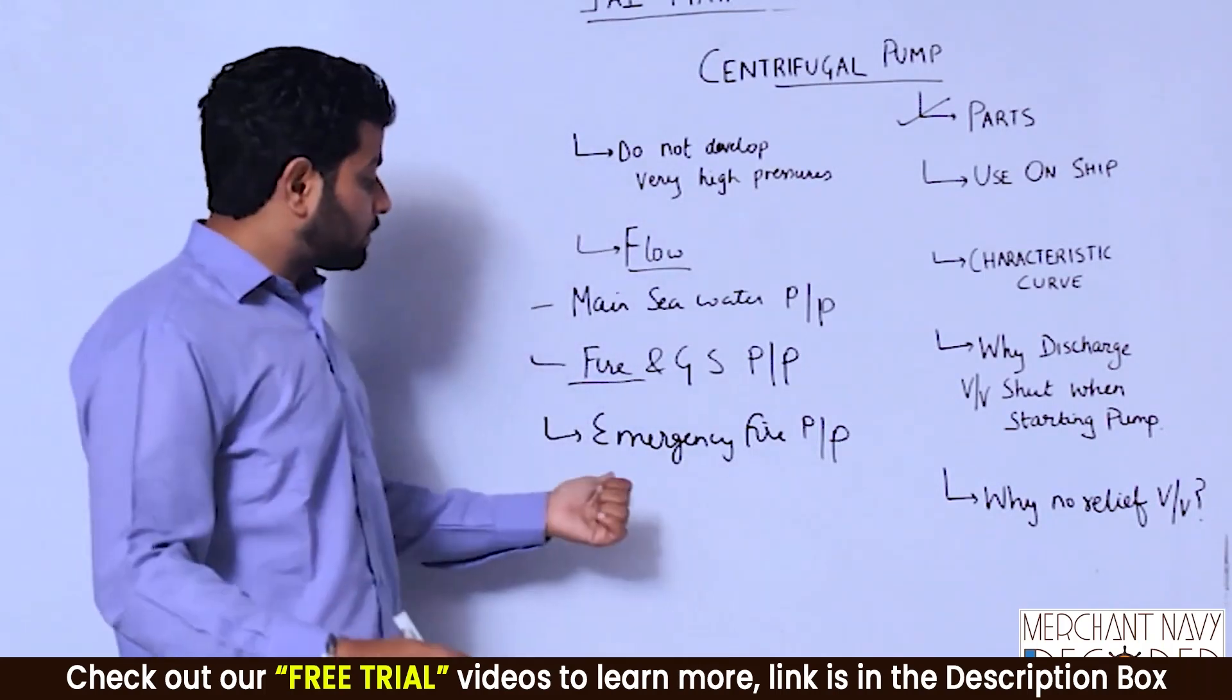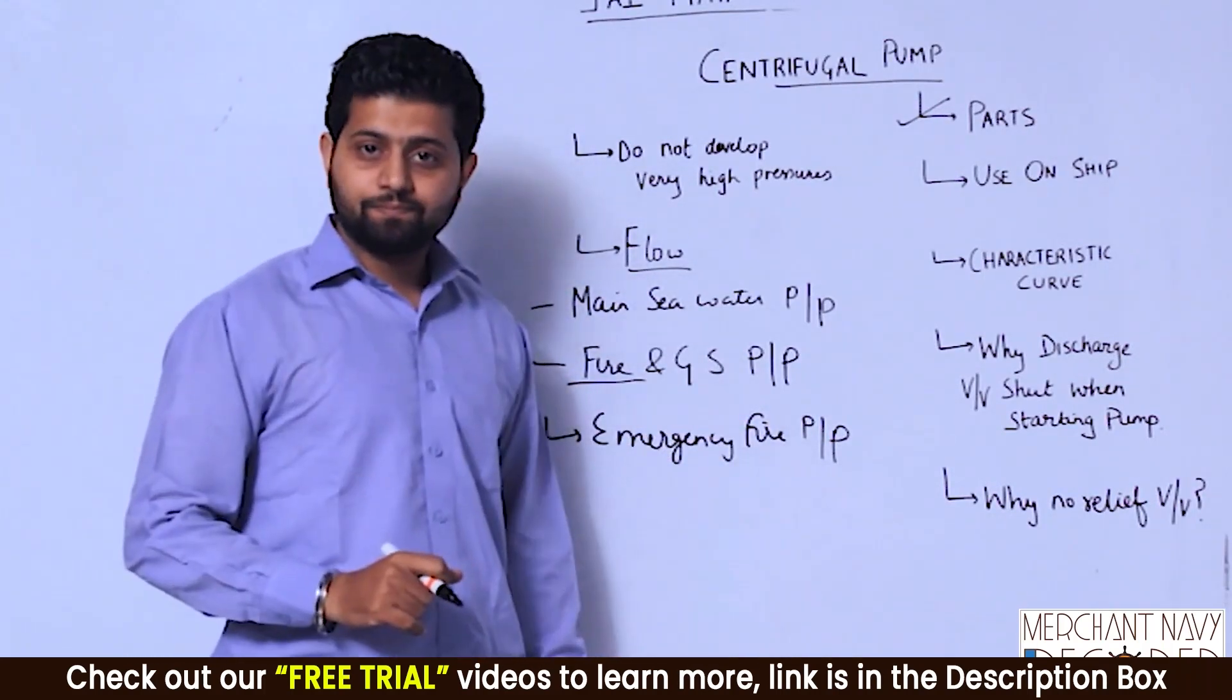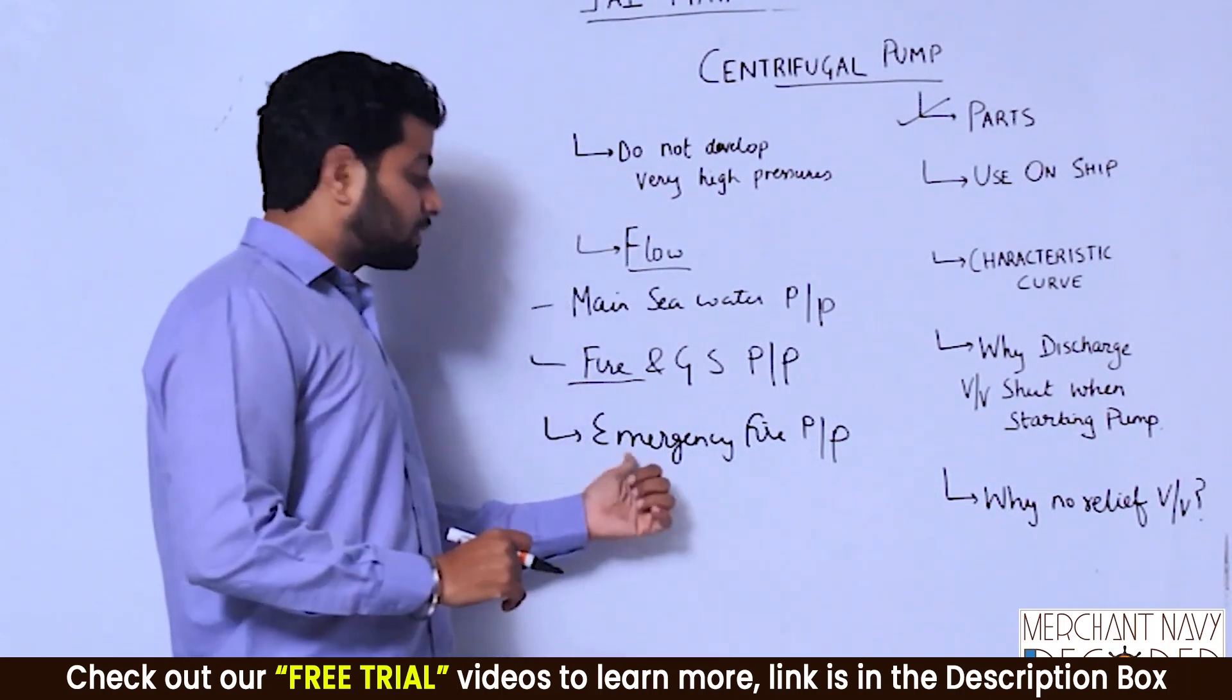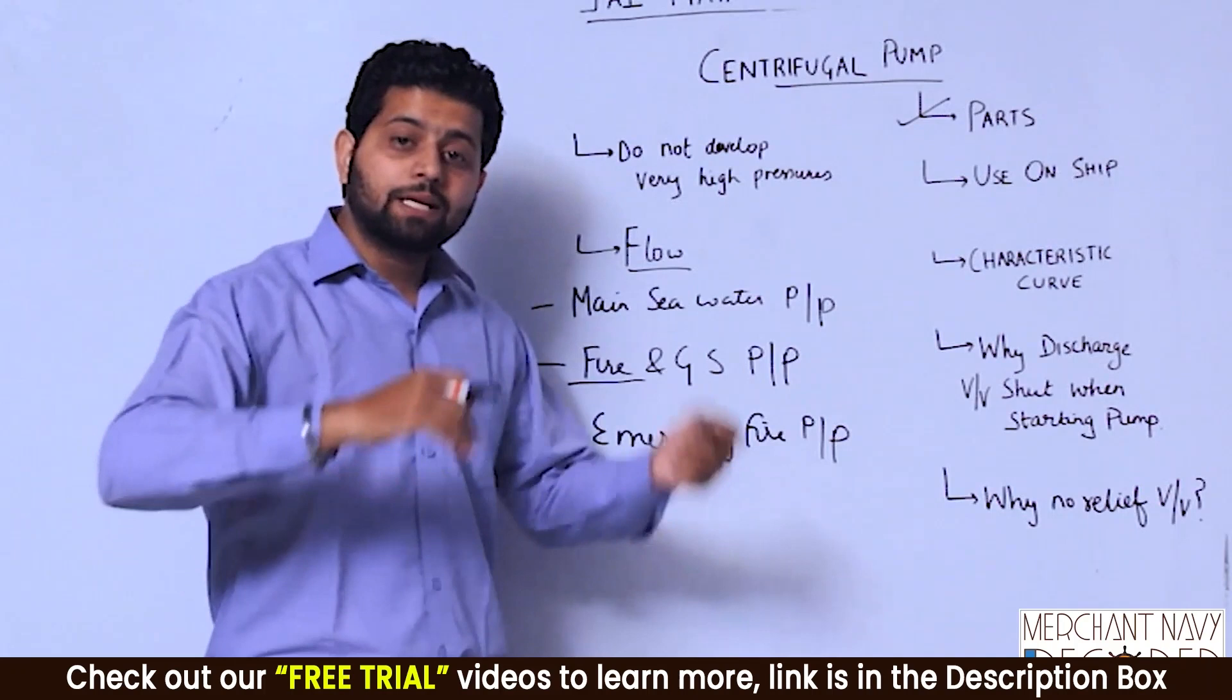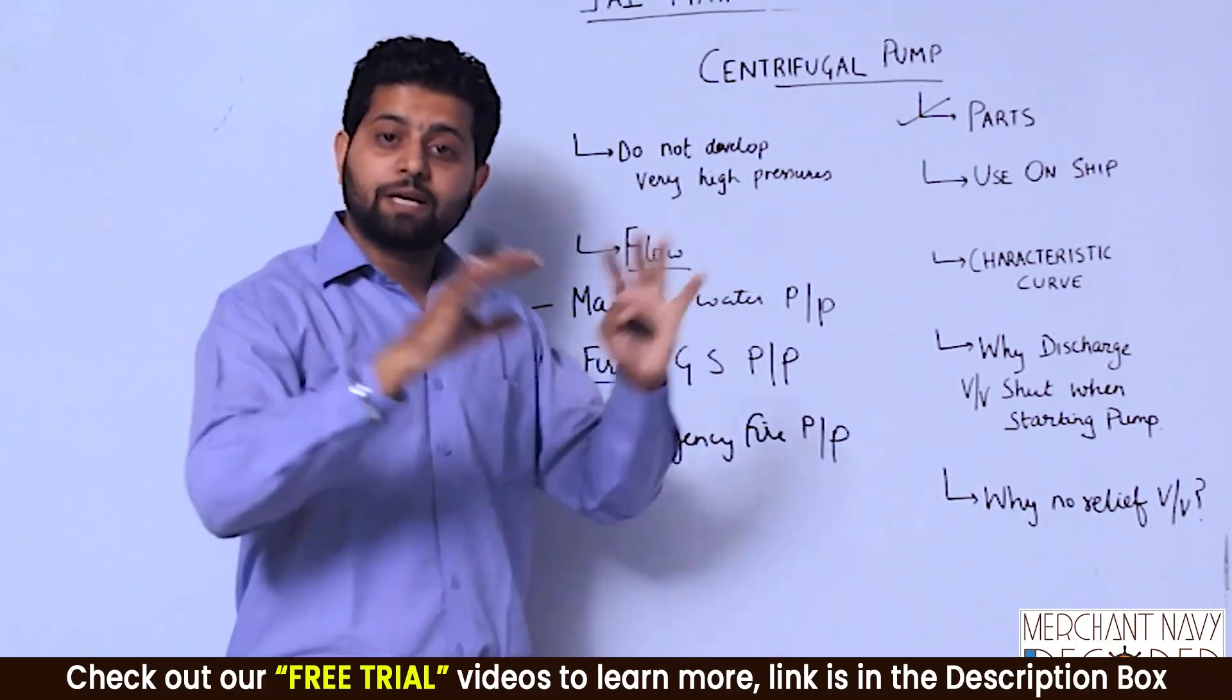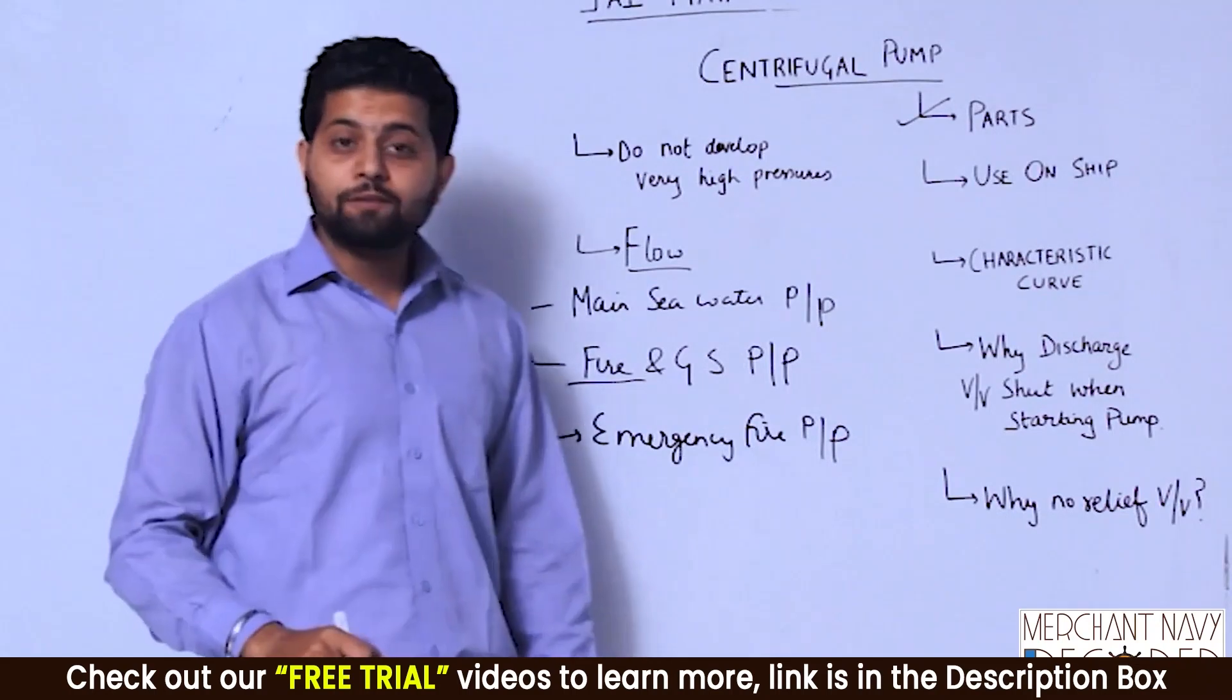So there is a separate pump called emergency fire pump fitted outside the engine room. It has supply from the emergency generator, not from the main generator. We assume that we cannot enter the engine room. So this is also a centrifugal pump.